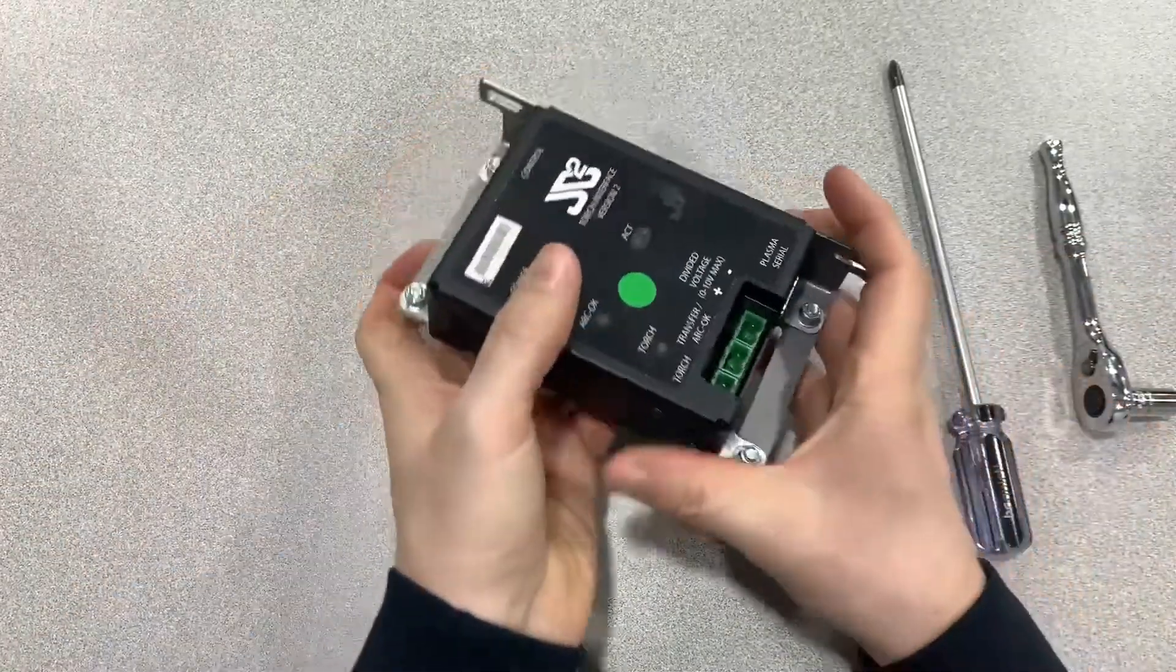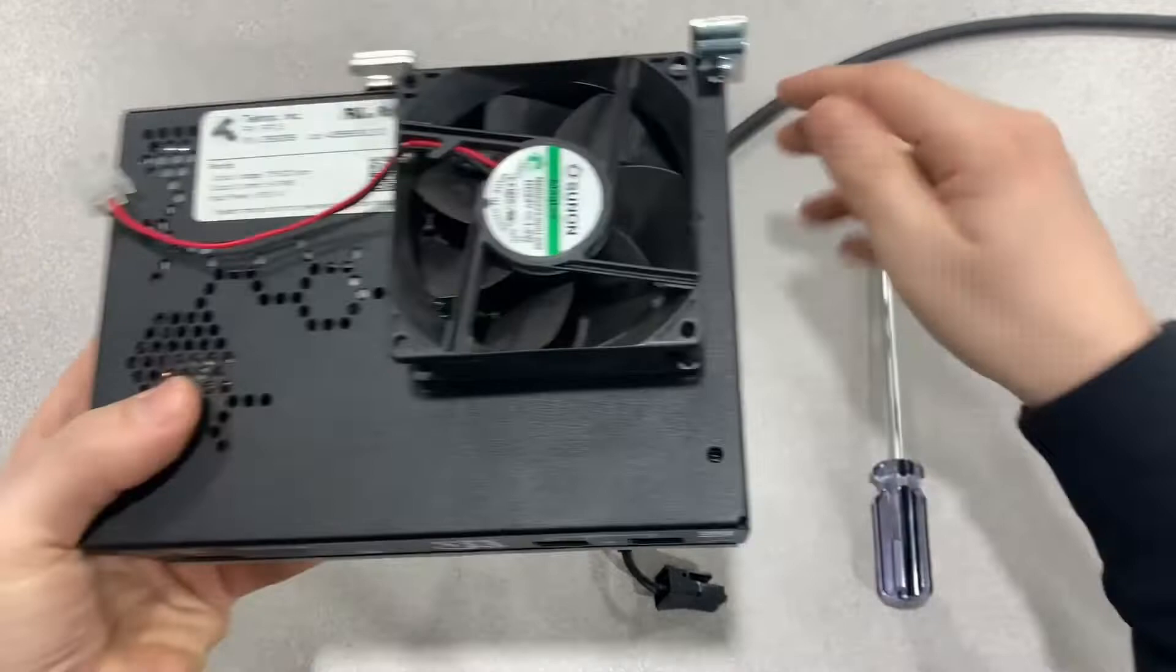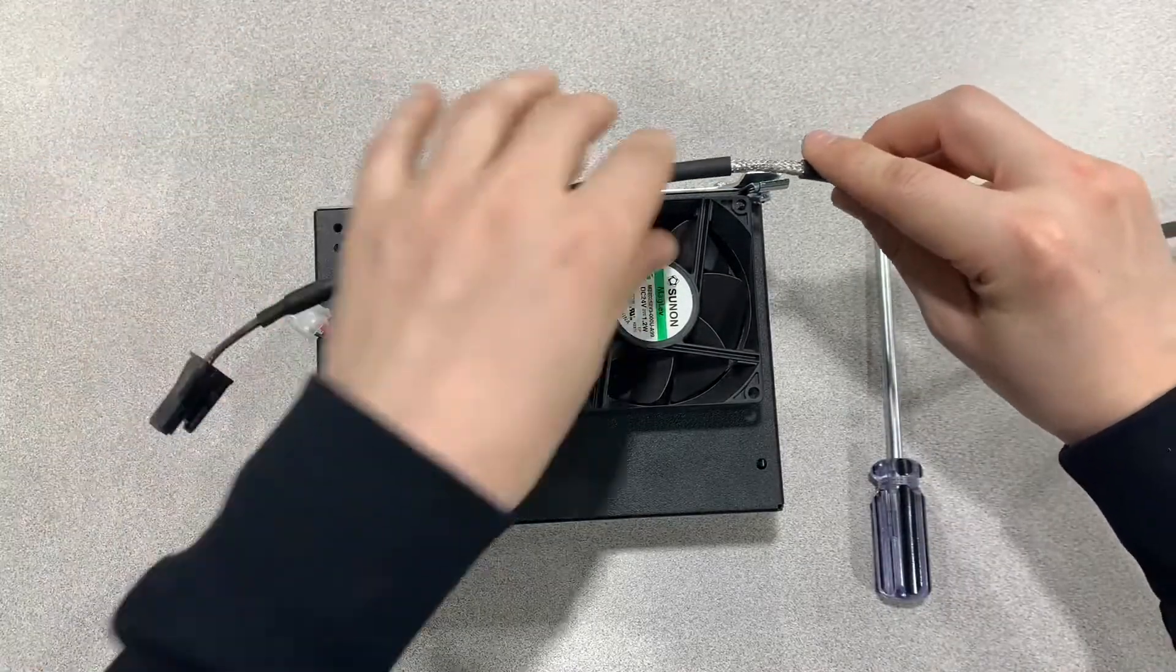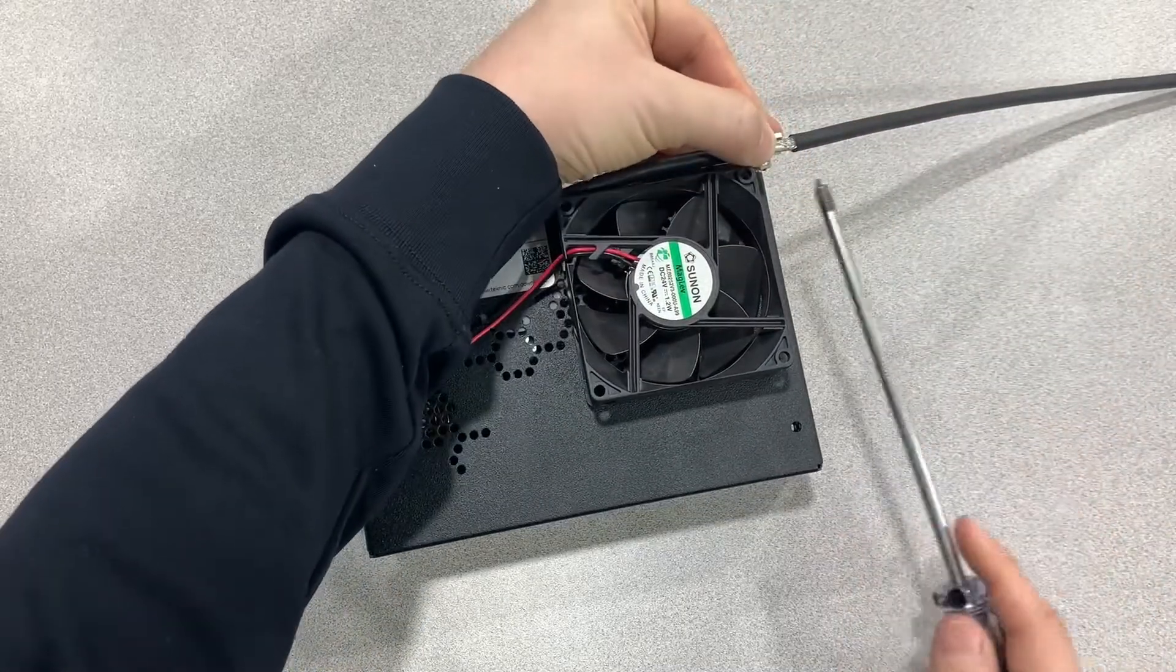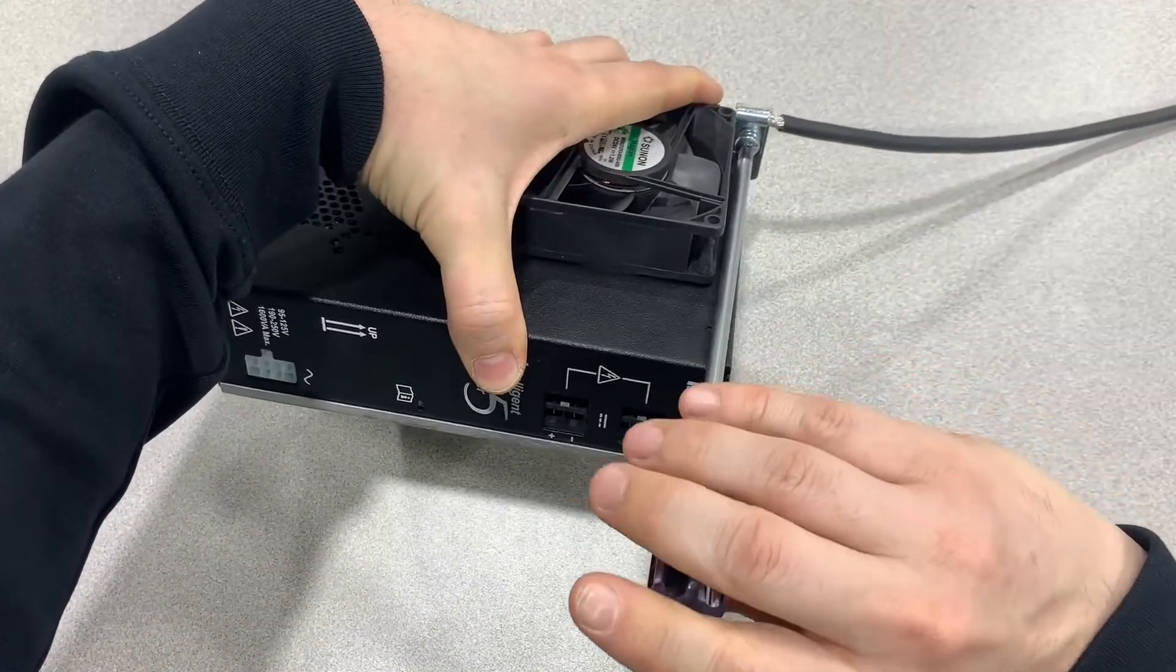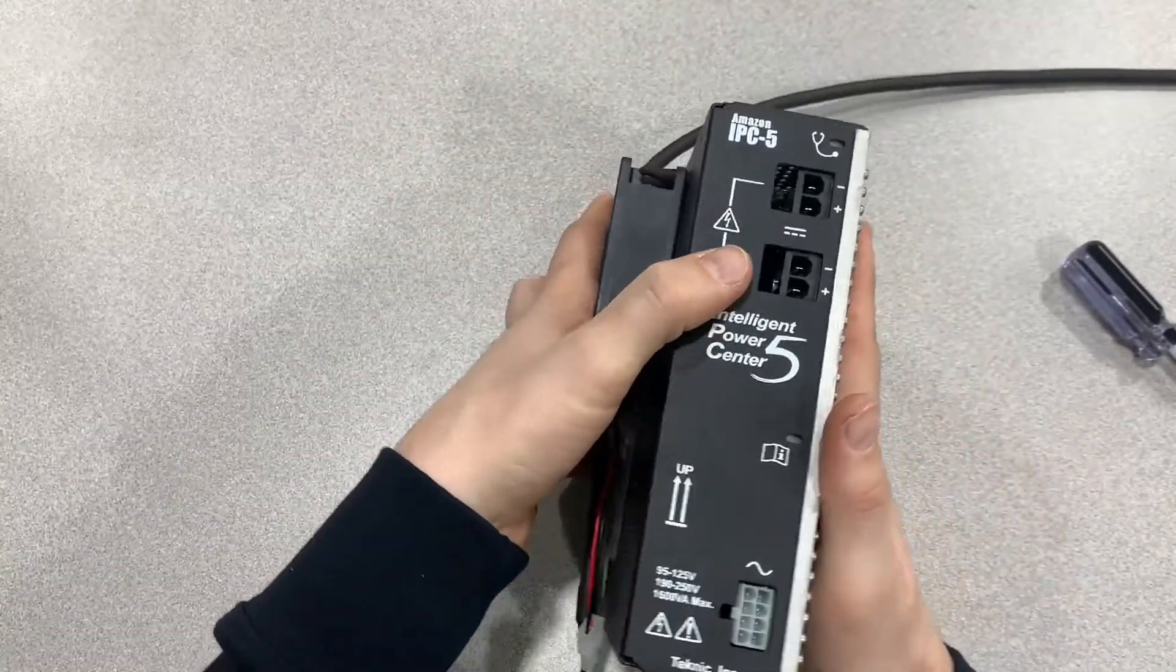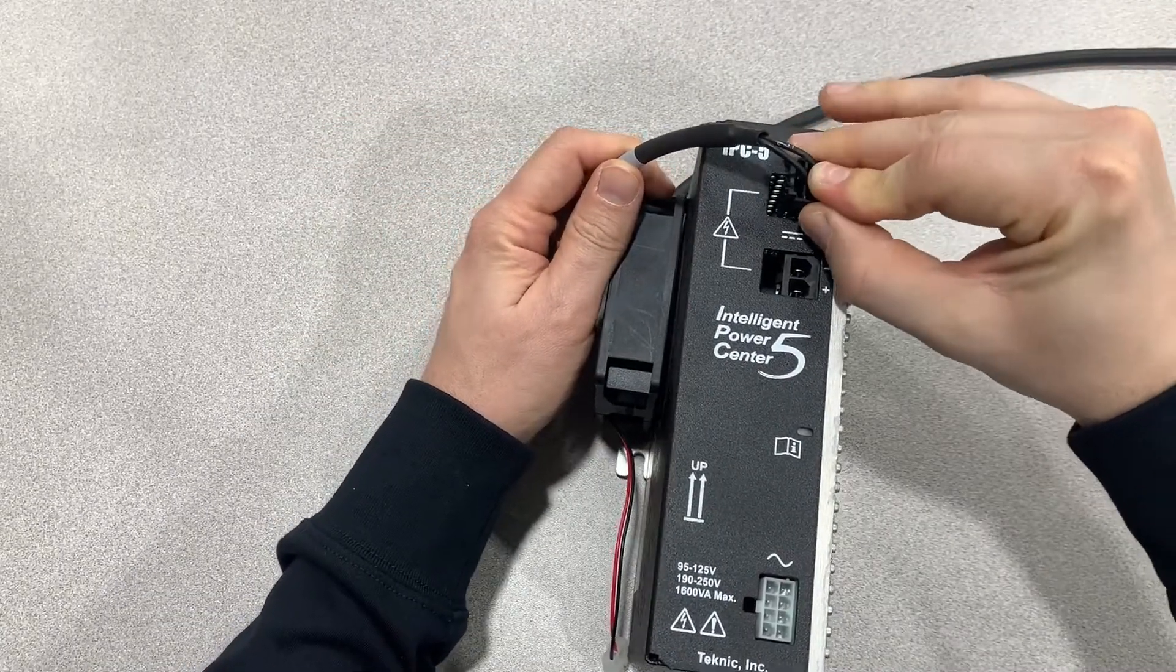We can now set the torch interface aside while we prepare the power supply. Due to space constraints inside the control panel, it is much easier to connect the servo power supply cable to the servo power supply before attaching it to the back plane. The servo power supply cable has a small window in the outer jacket removed exposing the braided shielding. Install this window into the clamp on the power supply bracket. Make sure that the wire is totally encompassed in the round section of the clamp and that we are not going to pinch any wires while tightening it down. Tighten it snug, but do not over tighten because you can damage the cable. Loop the cable over the fan and insert into the top connector location. The connector is keyed and cannot be plugged in backwards.